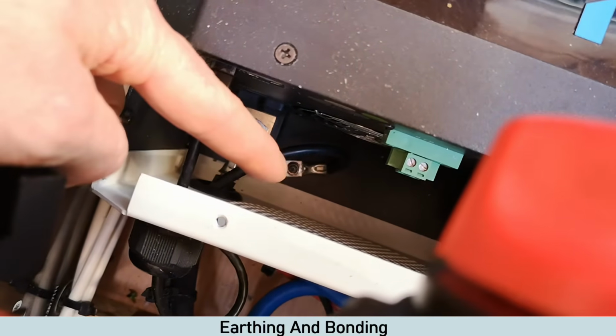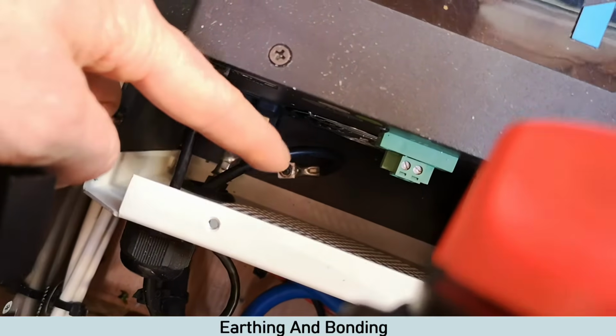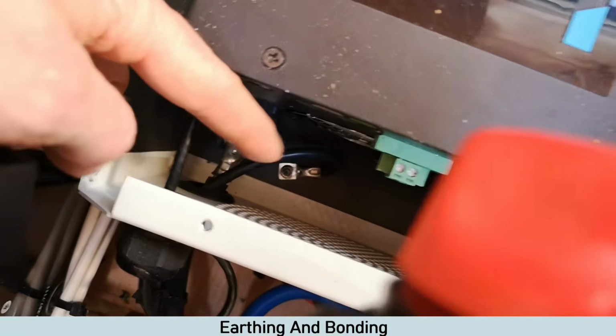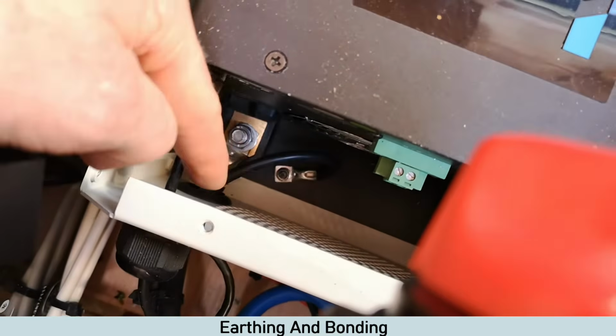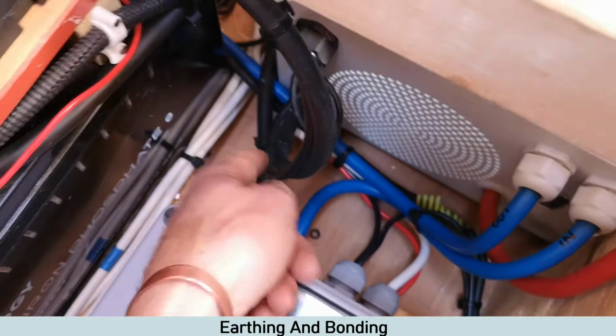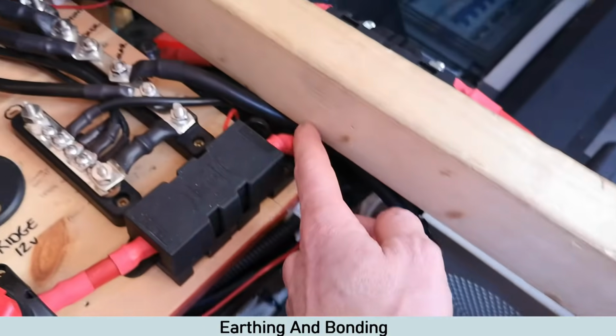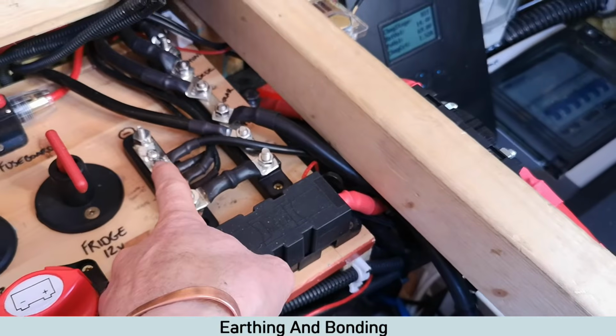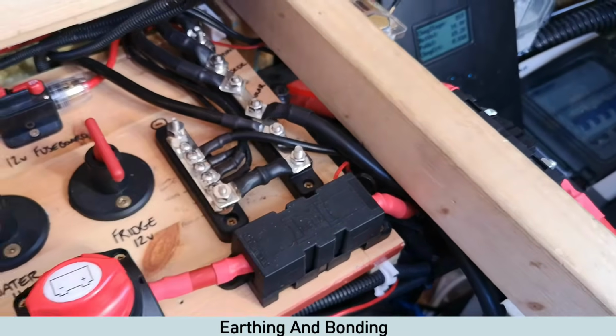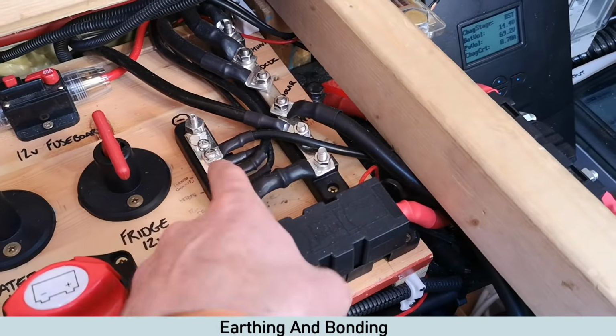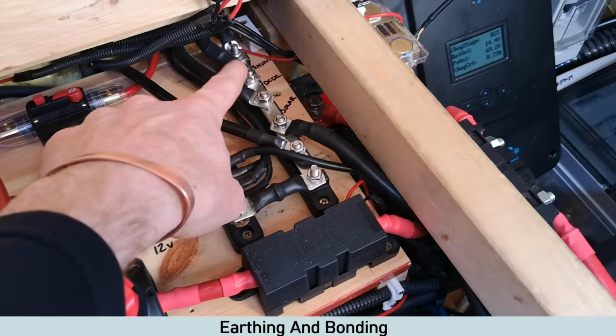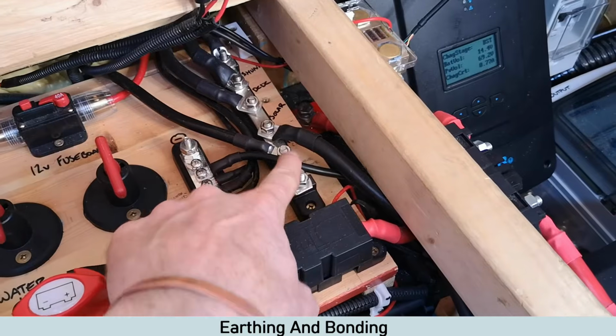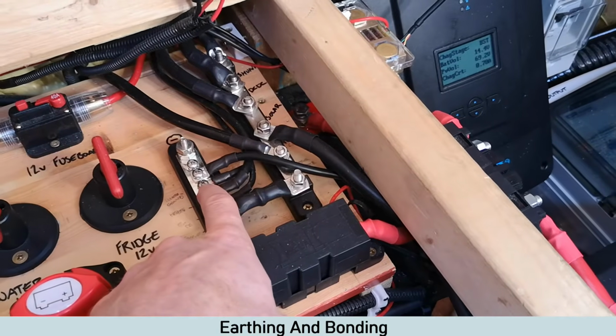It's an M4 bolt, that one is there, and then our cable is 10mm, so 8 gauge, and what it does, it routes from there through the same hole as the battery cable up here, and it actually connects onto our negative busbar. So the reason we've done that again is we've got a big cable which goes from here down to the chassis. So this cable connects to the chassis via the negative busbar.